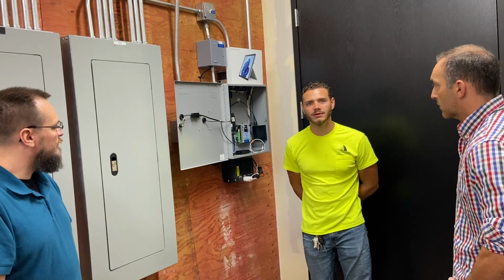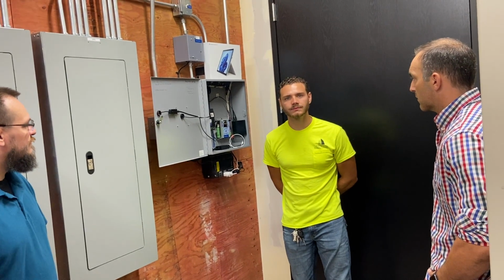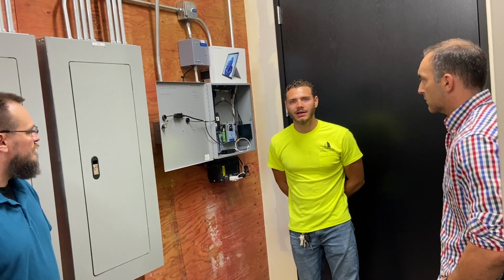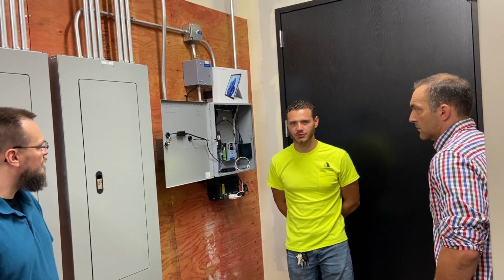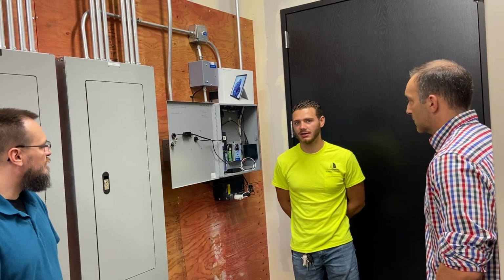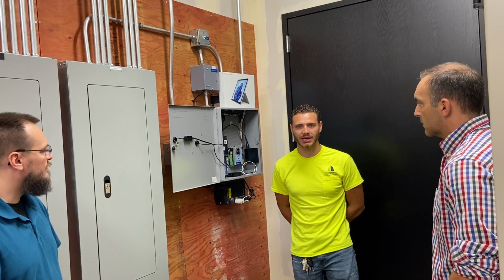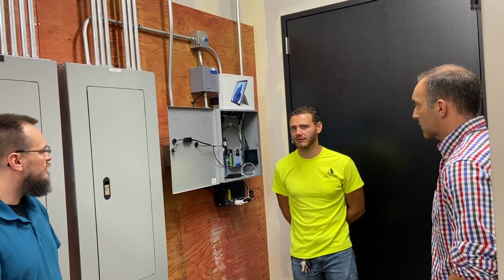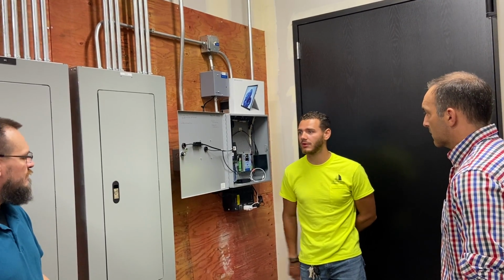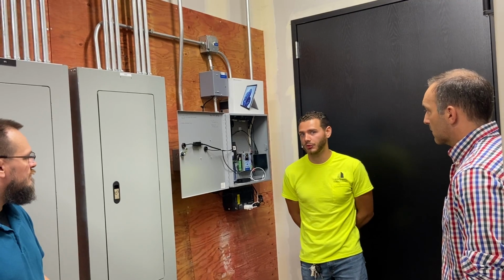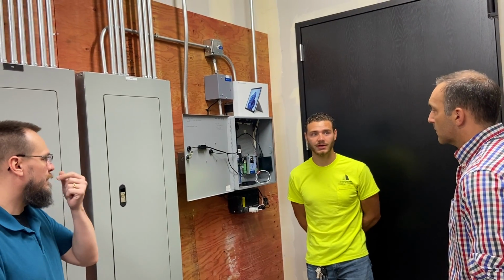Is there a way we can set it up so there's some sort of audible alarm, if that's an option they wanted? If something quits working, it starts beeping over here or something? Yes, we've made something like that happen before in a different situation, where if it turned off we had a red light that would beep and make a noise. With the amount of equipment we have, it would be a little involved, but I'd definitely ask and see if we could make that happen, or see if there's a way to adjust the program to send out an SMS or something if something was to fail.